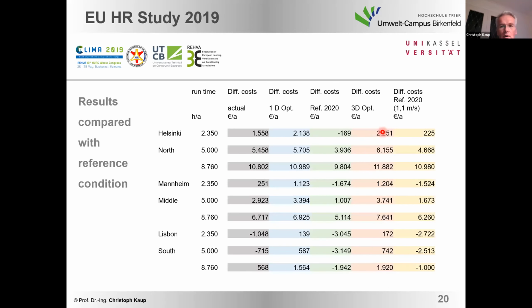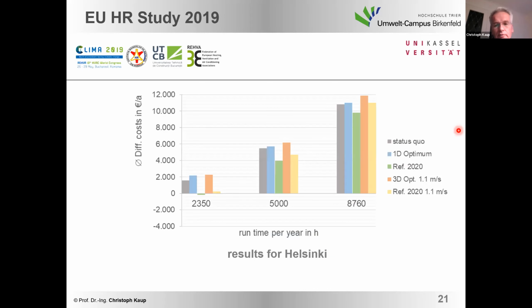And we calculated also the influence of these different several conditions. It's a table, very hard to understand, but the graph shows the same, but much easier to understand. The gray column shows the status quo, the blue column the 1D optimization, the orange column the 3D optimization, and green is the reference condition under the sizes of the actual status quo, and the yellow column shows the reference conditions if we would use the very low velocities of the 3D optimum. The 3D optimum was found roughly plus minus at 1.1 meter per second to keep the pressure loss as low as possible.